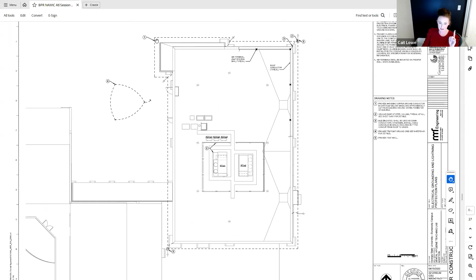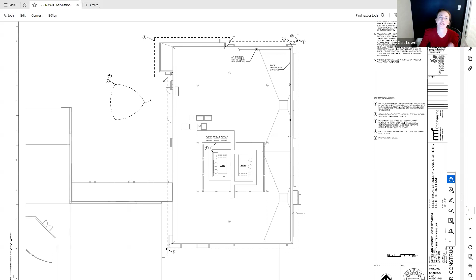And then I see another little note. Remember we talked about that grounding? Your grounding wire actually goes around the whole building and then away from your building and then loops again. And the reason it does that, you'll see these little dashed lines, this is actually your grounding. These 2s and 3s are the copper, it goes 10 feet into the ground. And then you'll see a separate loop, and that is a security loop. So if lightning actually hits your building, even if you don't have lightning protection, it's going to travel through that copper and into these loops to protect everything in the building.